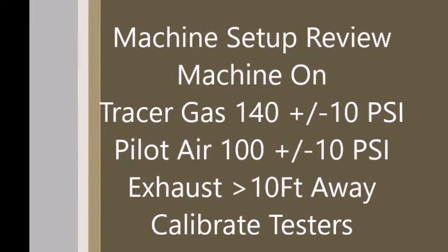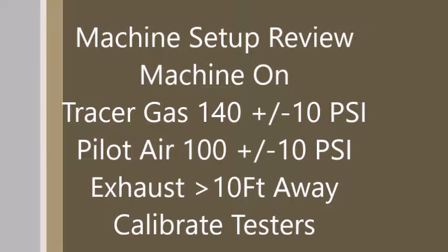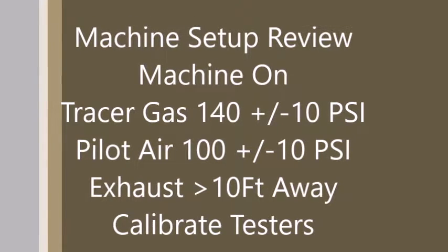Let's pause and review the machine setup at this time. Is the machine powered on? Is the hydrogen gas pressure 140 plus or minus 10 psi and the pilot air hose connected to the shop nitrogen at 100 plus or minus 10 psi? The exhaust hose must be at least 10 feet away from the testing area and make sure to calibrate the testers. When you are ready, move on to the next section.